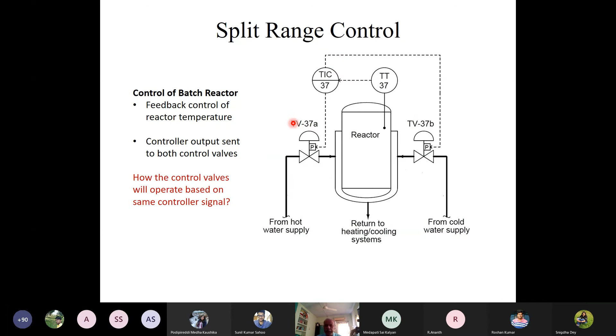Now the question is how these control valves will operate based on the same control signal. This strategy is basically called split range control. That means the controller output is going to multiple manipulated variables, and the way in which this splitting of the controller signal is made is called the split range control strategy.